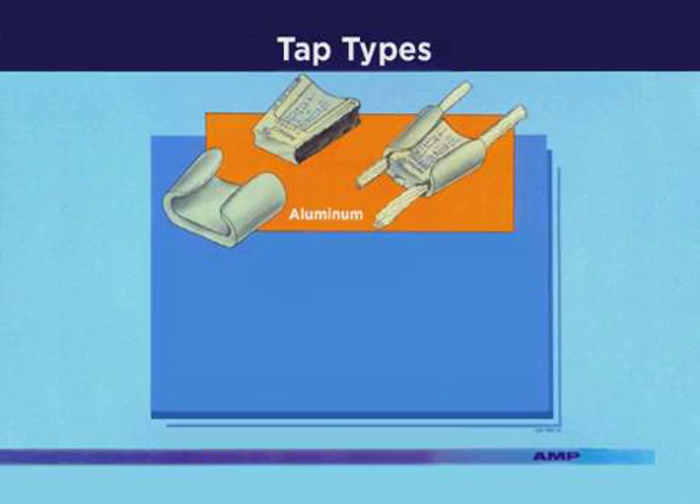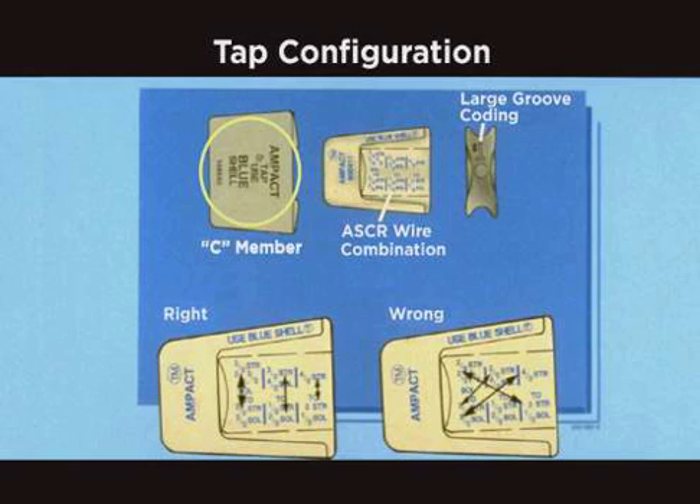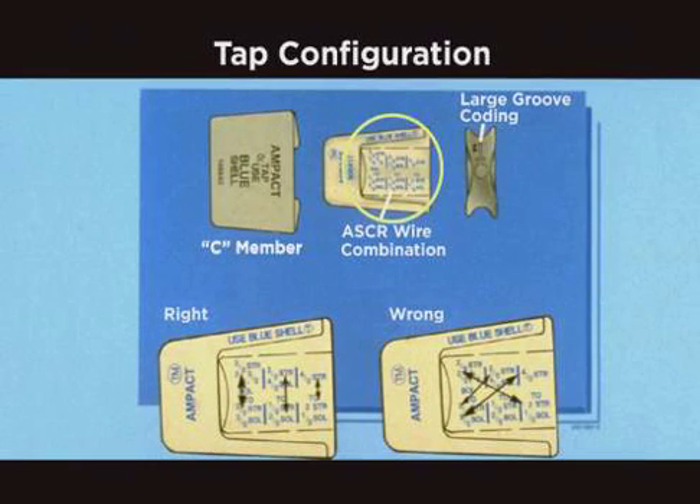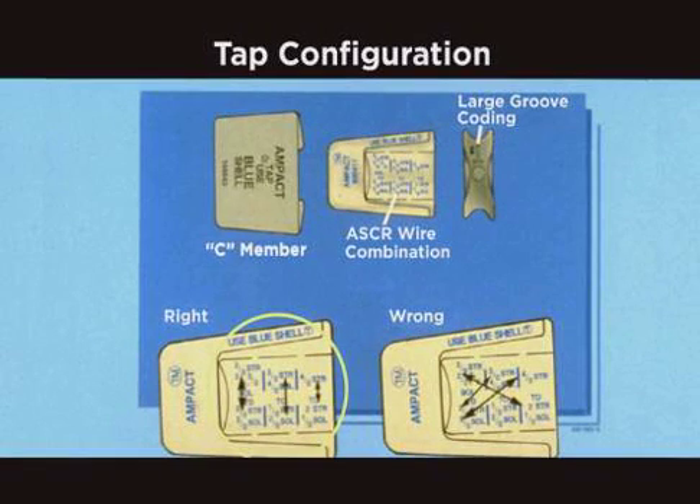Both types are available to cover a wide range of wire sizes. The aluminum TAPs can be used on various types of wires including AAAC and ACSR. Listed on the back of the C member is the correct color-coded shell to be used. Listed on the tapered wedge are the various wire sizes to accommodate the large variety of wire combinations. The large wire groove is also coded. Markings are printed to be read up and down the column, not diagonally.